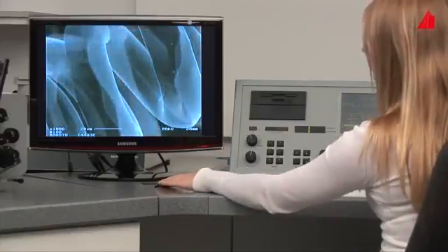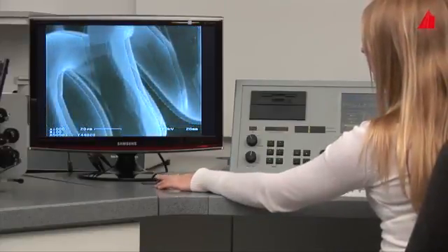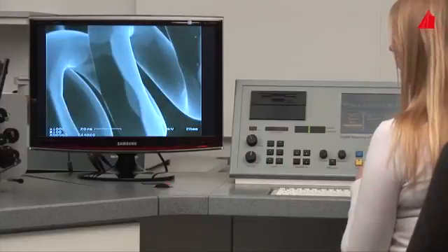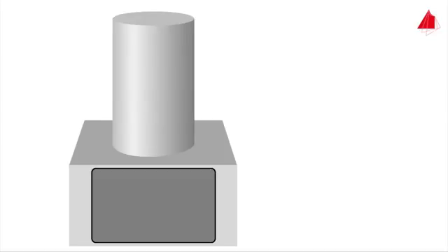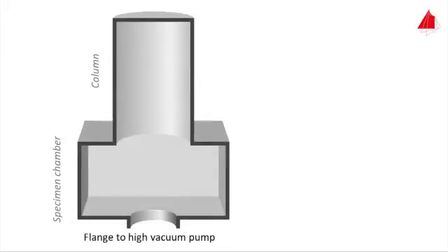But how is this plastic image generated, and how does the microscope actually function internally? The animation first shows the schematic structure from the outside. The upper part is the so-called column. It is used to generate an electron beam. The lower part consists of the specimen chamber with cover plate. In the longitudinal section, the flange leading to the high vacuum pump is visible at the bottom. Thereby, high vacuum is generated inside the whole microscope.